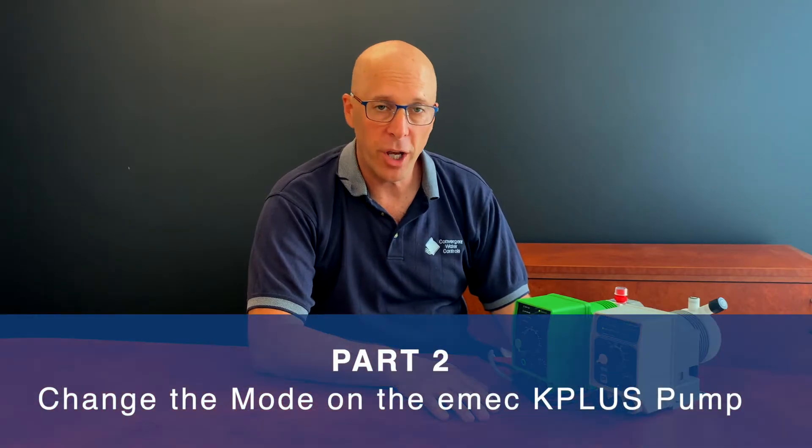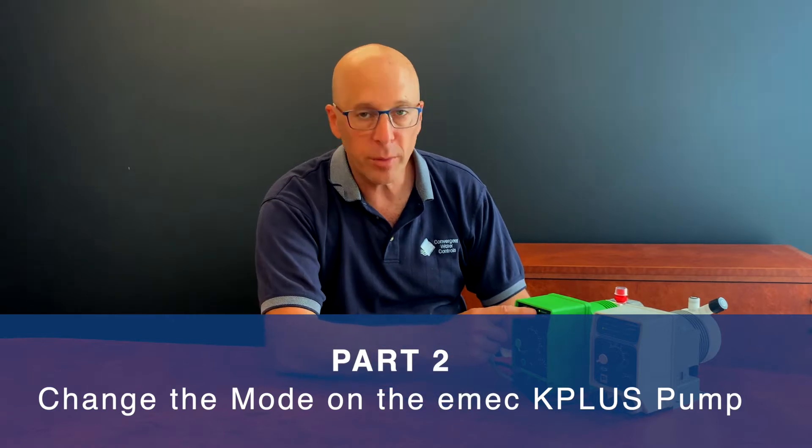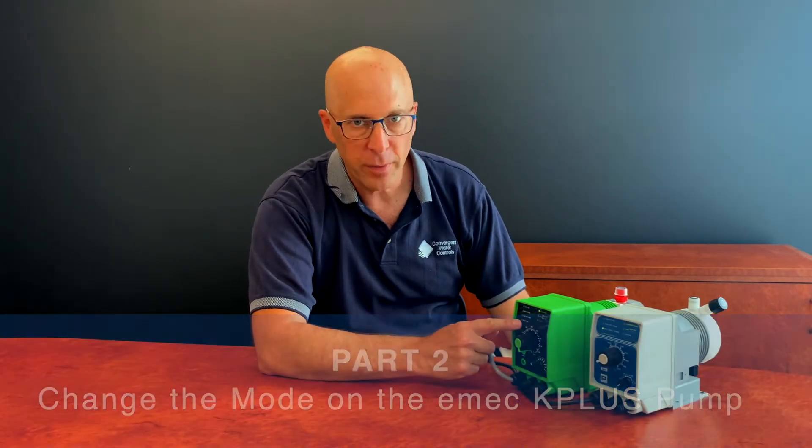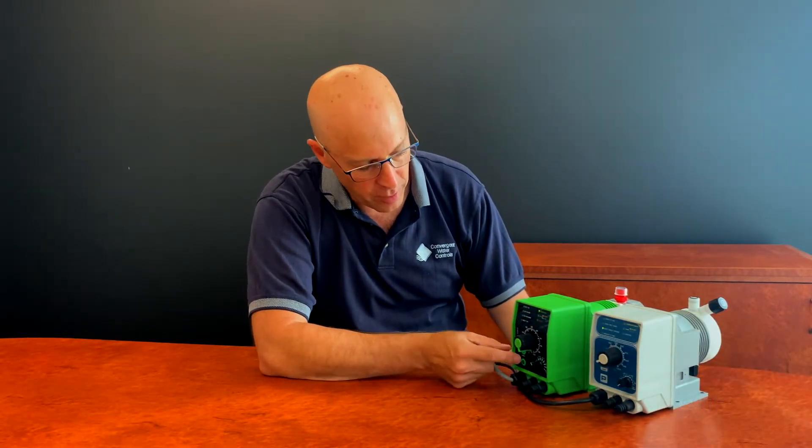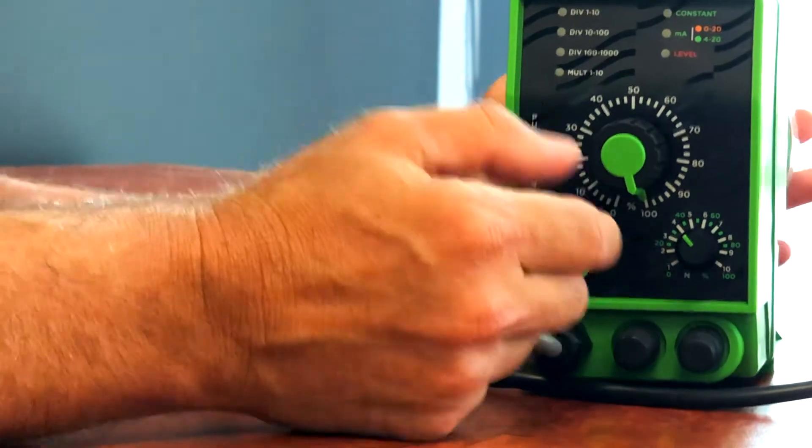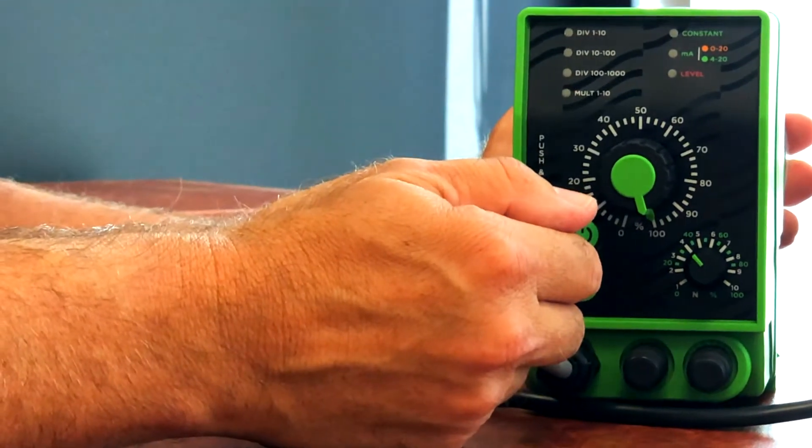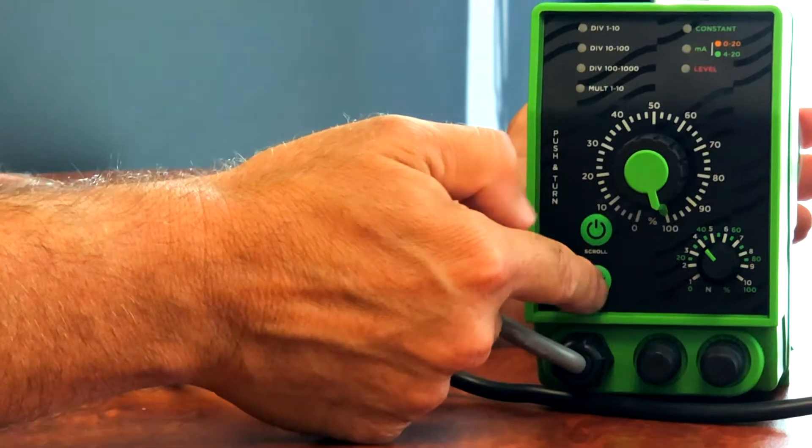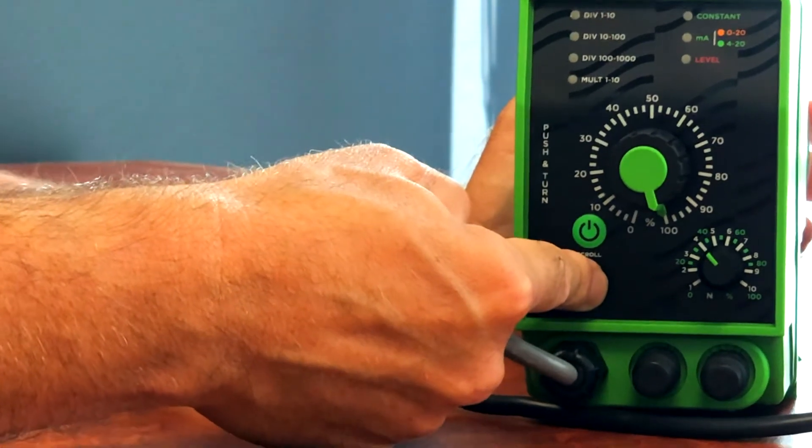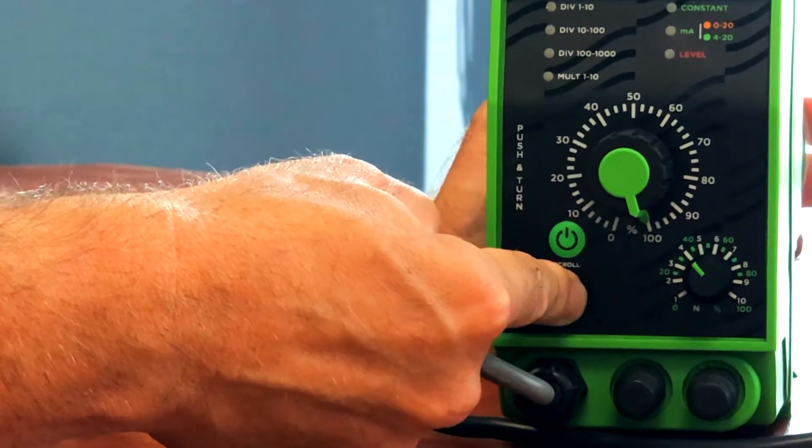I'm now going to explain how to change the mode on the pump from constant mode to multiply mode. So the first step is to press the power button once, which puts the pump into standby. We then hold the programming button, or the settings button, down constantly until all the LEDs flash.